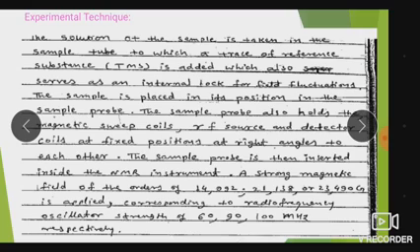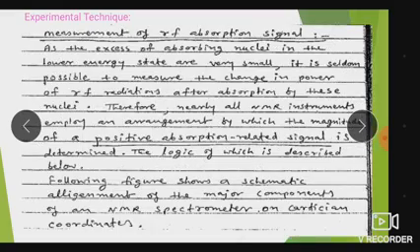A strong magnetic field of the order of about 14,092 gauss, 21,138 gauss, or 23,490 gauss is applied, corresponding to a radio frequency oscillator strength of about 60, 90 and 100 megahertz respectively, depending upon the field strength.